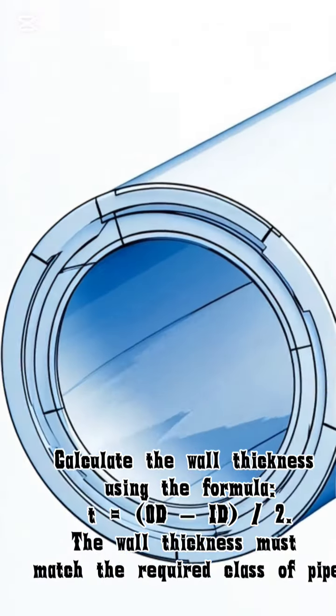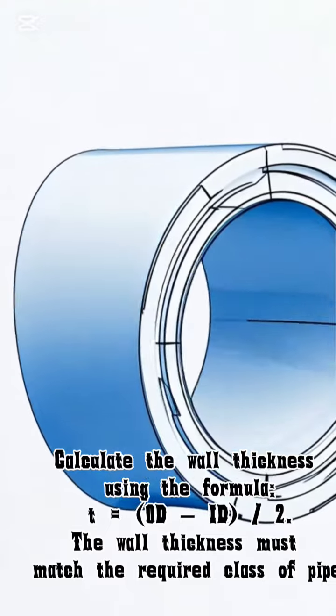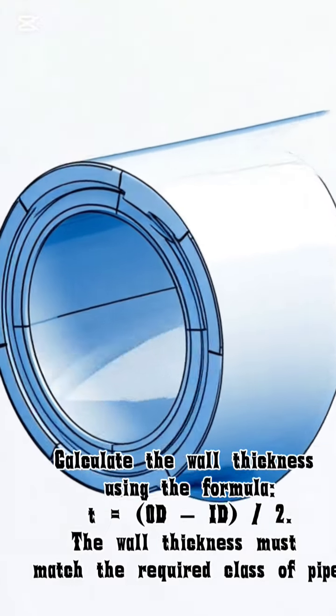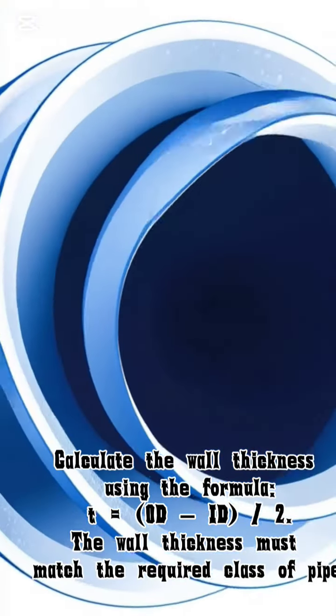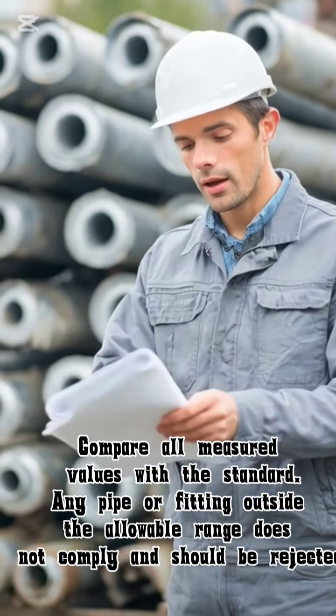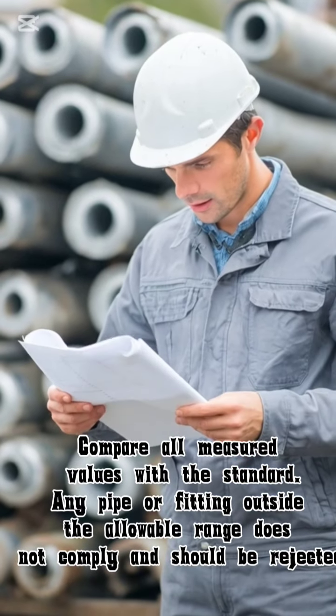Calculate the wall thickness using the formula T equals OD minus ID, divided by two. The wall thickness must match the required class of pipe. Compare all measured values with the standard. Any pipe or fitting outside the allowable range does not comply and should be rejected.